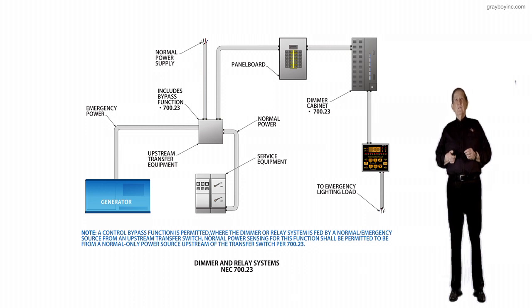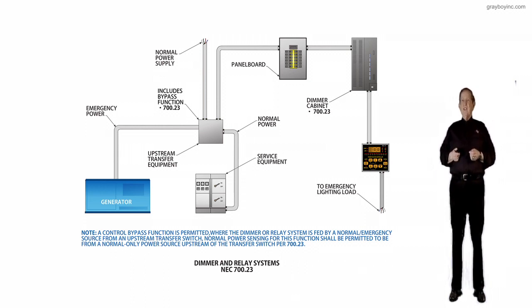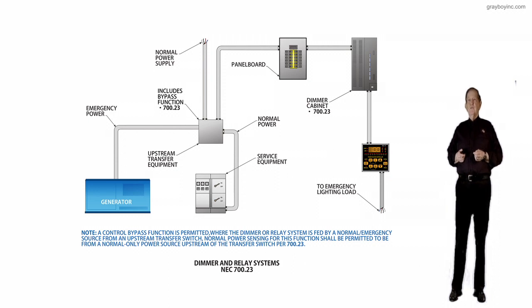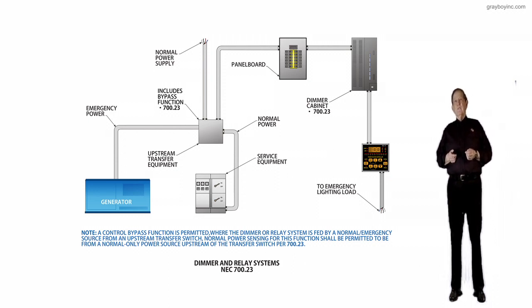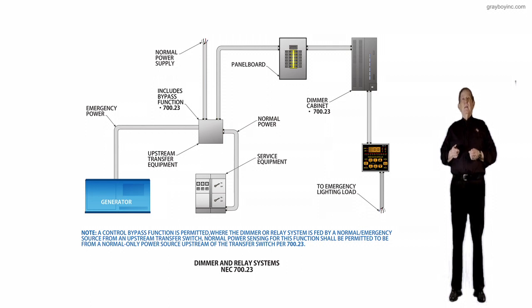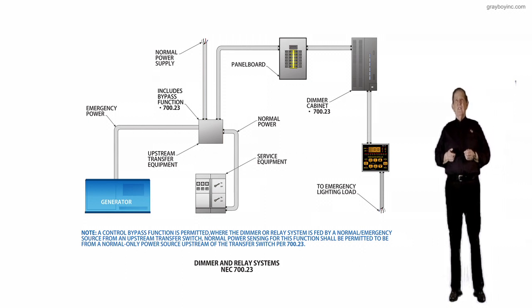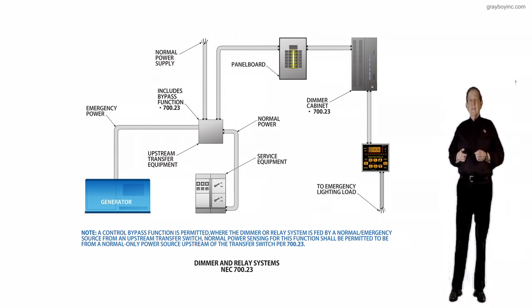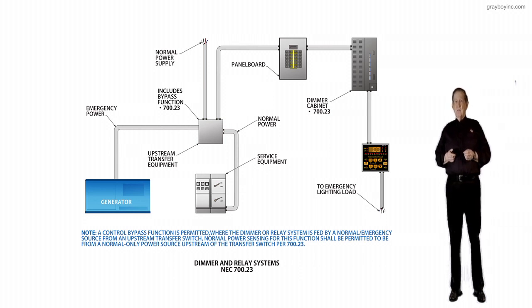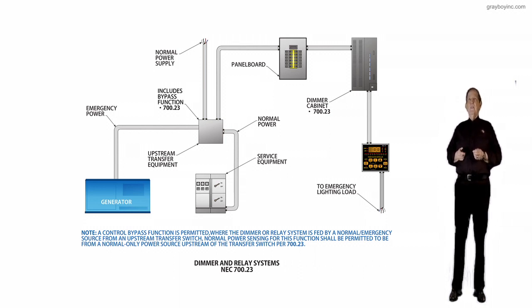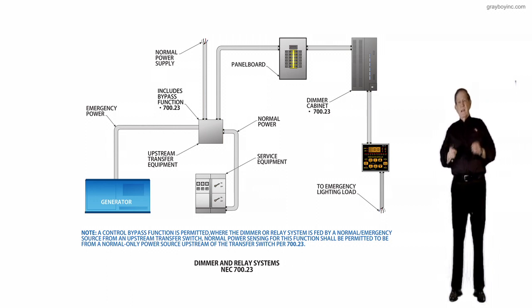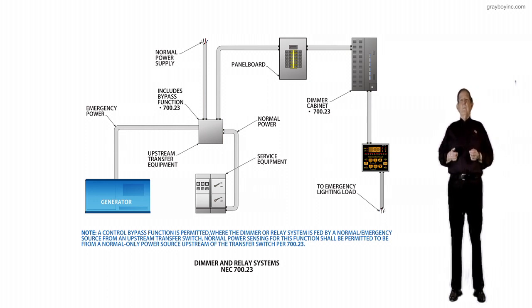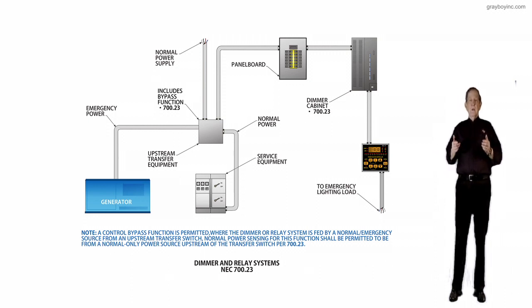Now, I would like to remind you of some other important sections that we do not have illustrations of, but we would like to call your attention to these changes. If you have a meter mounted transfer type switch, we would want to reference 700.5(A). If you were providing selective coordination, and that's required, then look at your figure 700.32, and that figure will give you a good illustration of how selective coordination would be provided.